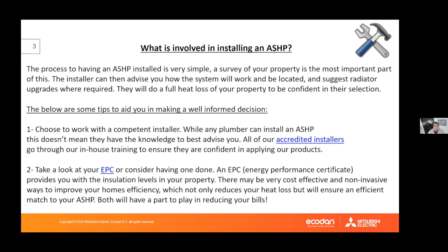The second most important thing is to find a competent installer. Any plumbing and heating engineer could install an air source heat pump, but they may lack the knowledge to design the system properly for the house. With gas boilers, sizing has traditionally been rule of thumb — plumbers know off the top of their head what size boiler and radiator to put in — and historically it was always oversized because gas was cheap and boiler price differences were minimal. That approach won't work for air source heat pumps, where moving up a unit size increases both equipment and installation costs.